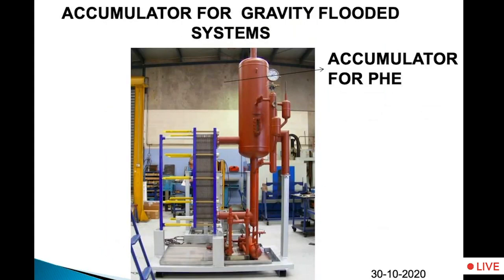And as I show you in this slide, there is a PHE, plate heat exchanger, and the accumulator. The accumulator is mounted so that there is a liquid. The PHE is full of liquid. Lot of people fill up the vessels only up to 80%, and then they say, oh, we are afraid no liquid should come to the compressor, so we maintain our evaporator levels at 85%, which is wrong. Evaporator should be fully flooded and the level should be controlled in an accumulator. 85% evaporator liquid level will give you only 85% efficiency of the evaporator. So a fully flooded evaporator is a must, and accumulator location, accumulator diameter, accumulator sizing is an important calculation.